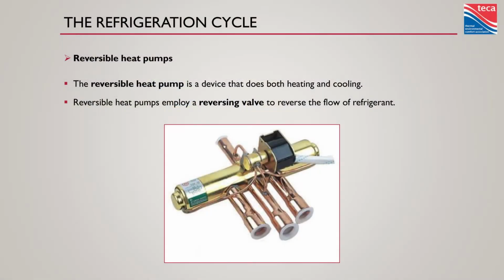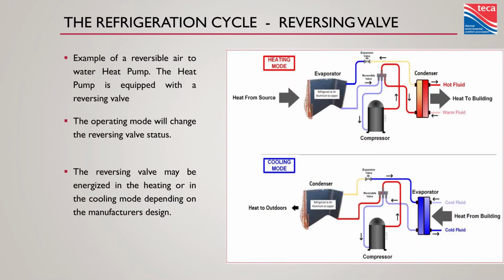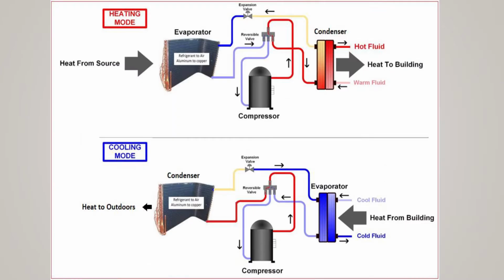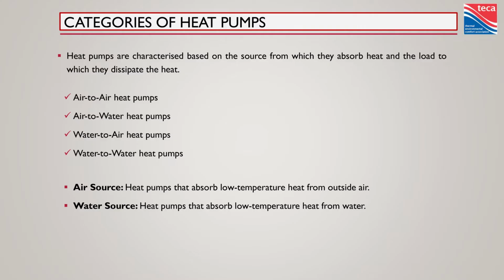Use the reversing valve. All the reversing valve does is change the direction of flow after it leaves the compressor. Simple stuff. Not going to get too far into it, but it leaves the compressor, goes through the reversing valve, takes a left or a right. Are we heating or are we cooling with that energy? But these are excellent candidates for cooling as well. We don't think of hydronics in cooling a lot, but we can. We can use chilled water to move thermal energy out of a building, and it's, again, high distribution efficiency, just like our radiant floor heating is. It's just hydronics. Instead of heated water, it's chilled water.